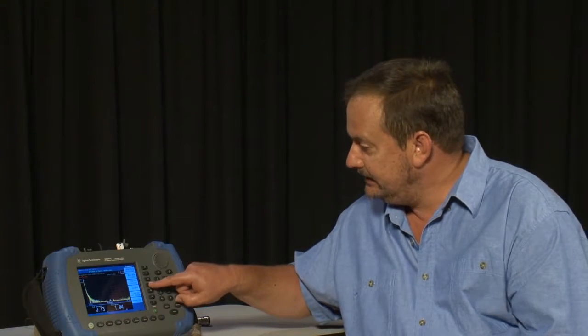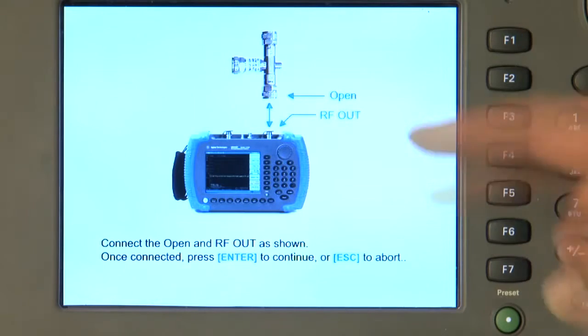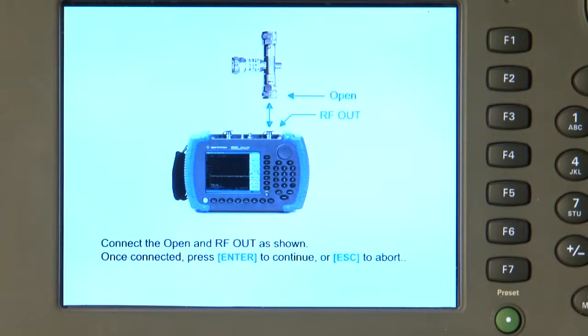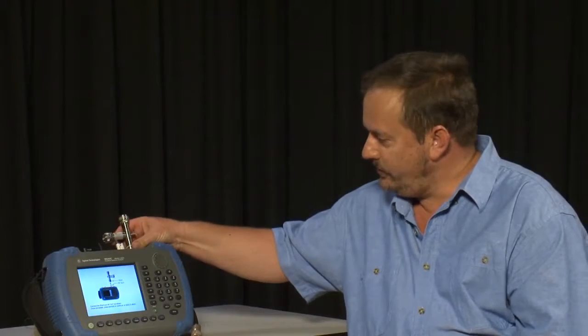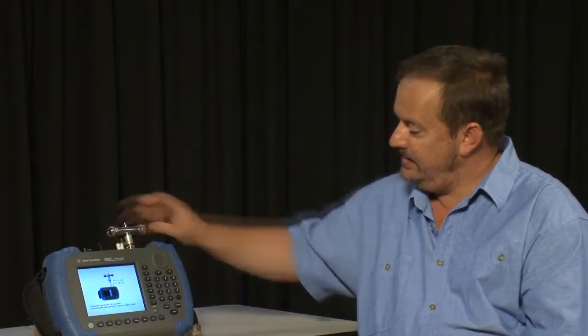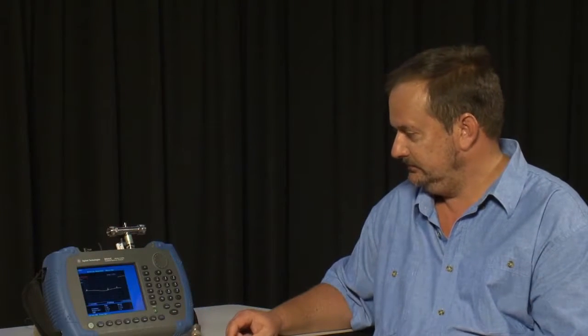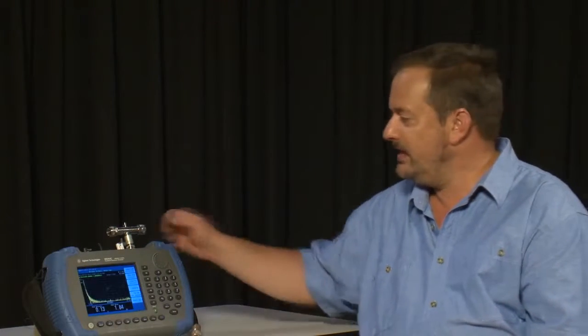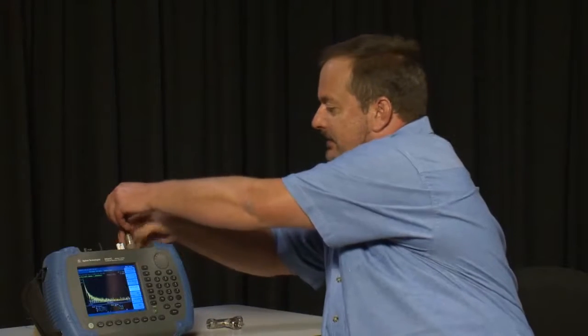Next, we need to perform a calibration like we did previously. So I will press Frequency and Calibrate and we just follow the instructions. So I will connect the Open and press Enter. We connect the Short and press Enter. And we connect the Load and press Enter. So the instrument is now calibrated. So all I have to do now is connect my cable.